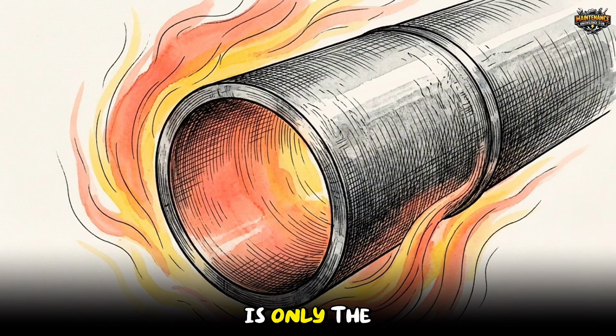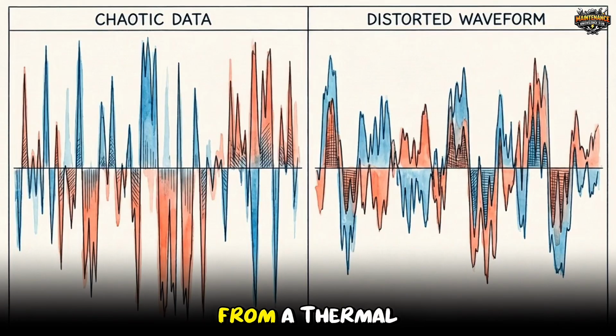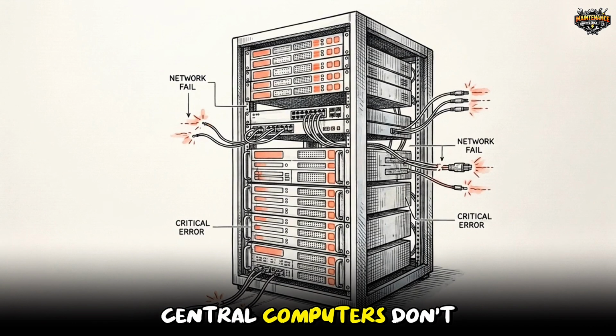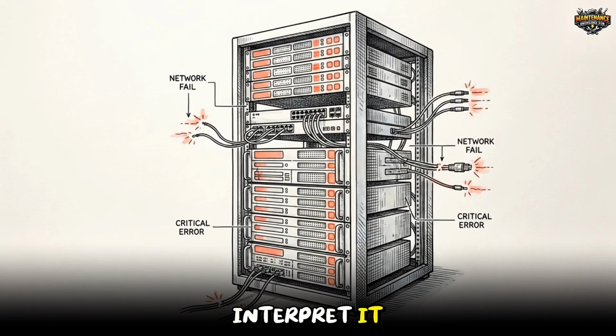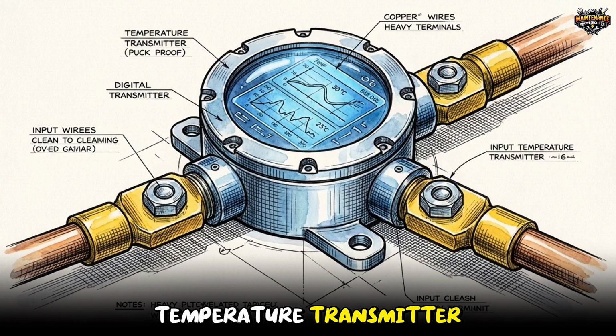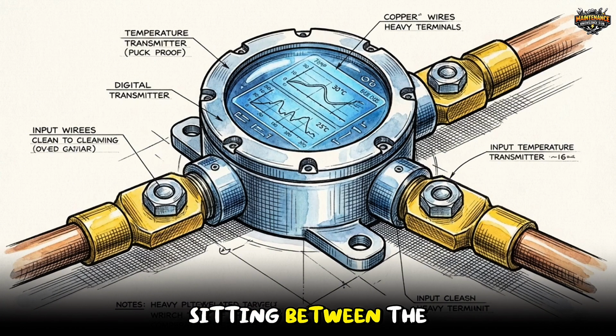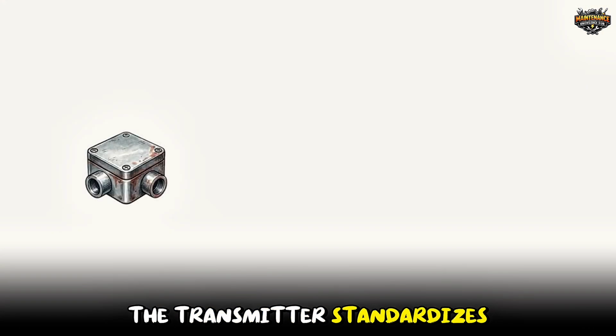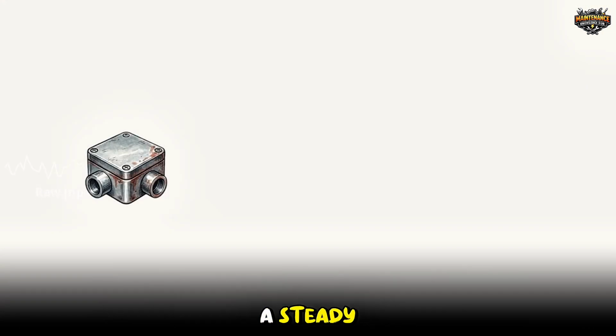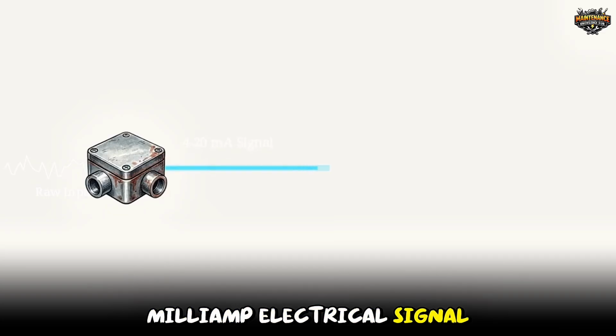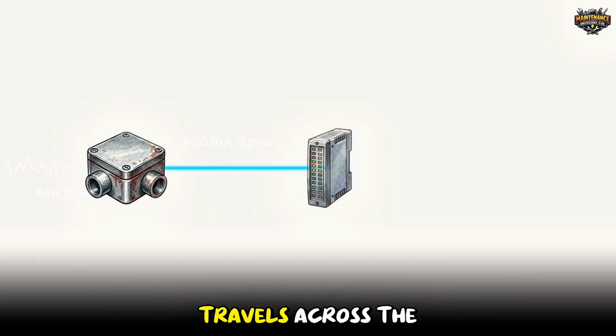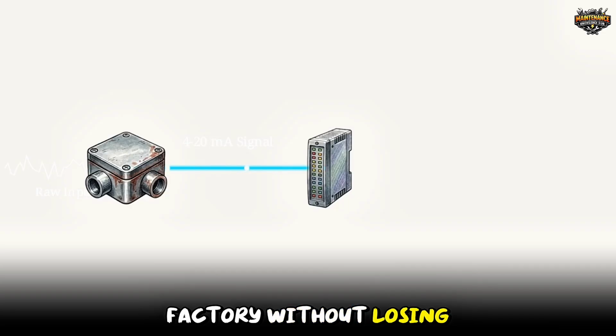Capturing the heat is only the first step. A raw pulse from a thermocouple or a fluctuating resistance from an RTD is completely useless if the plant's central computers don't know how to interpret it. That's why every industrial sensor connects to a temperature transmitter, a vital piece of hardware sitting between the raw physics and the digital network. The transmitter standardizes raw physical data into a steady 4 to 20 milliamp electrical signal. This robust current travels across the factory without losing accuracy.